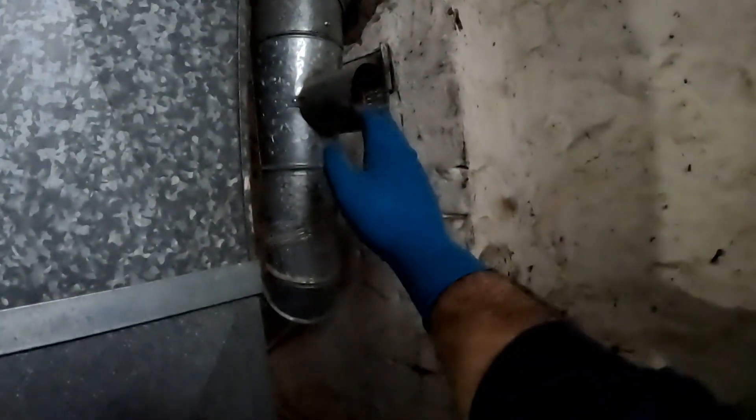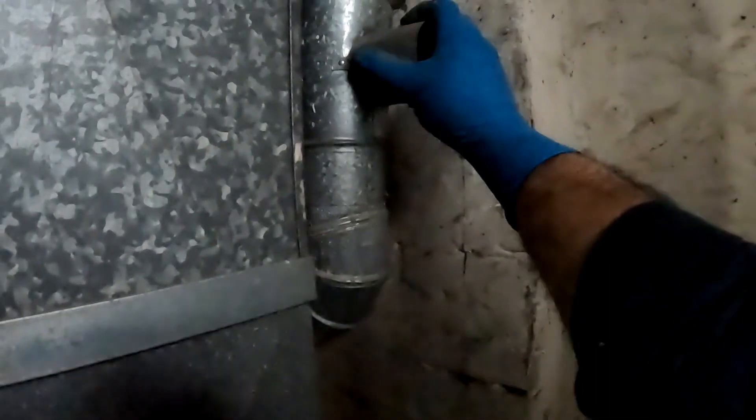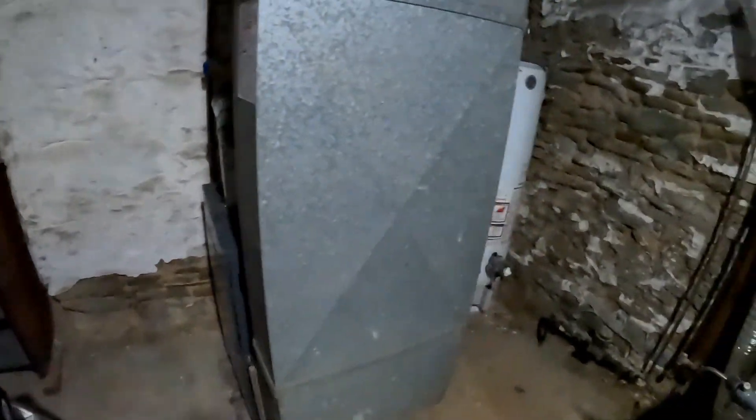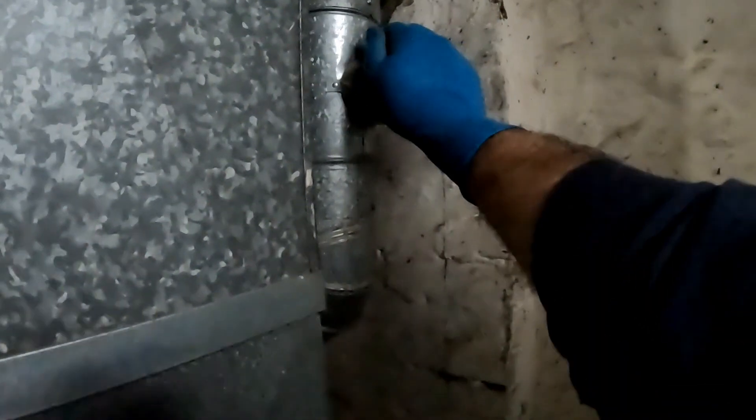The tank's drained, cut out. What occurred here is: when the inducer is running, it makes a suction, the pre-purge seals this off and makes a positive pressure — you lose your draft of the water heater until the furnace lights. This Goodman furnace is a hundred thousand BTU input, eighty thousand output. The five inch flue for the furnace alone is okay, but with the forty thousand BTU water heater added, you technically have a hundred forty thousand BTU. Anything above a hundred five thousand BTU requires a six inch flue — so this was undersized.